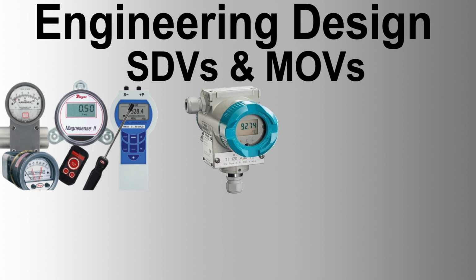Each actuator shall comprise a 3-phase electric motor, reduction gearing, reversing contactor starter complete with local controls, adjustable torque limitation facilities, electronic logic controls, and monitoring facilities, all housed in a double-sealed watertight enclosure to a minimum of IP65. Actuators shall be suitable for use on a 415-volt, 3-phase, 50 Hz power supply.